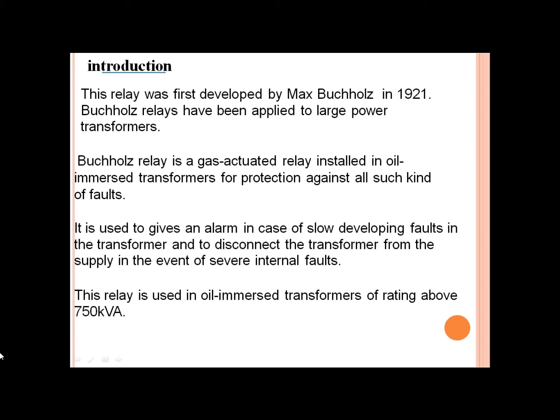It is basically a gas actuated relay installed in an oil-immersed transformer for protection against all such kinds of faults. It is used to give an alarm in case of slow developing faults in the transformer and to disconnect the transformer from the supply in the event of severe internal faults. This relay is used in oil-immersed transformers of rating above 750 KVA.